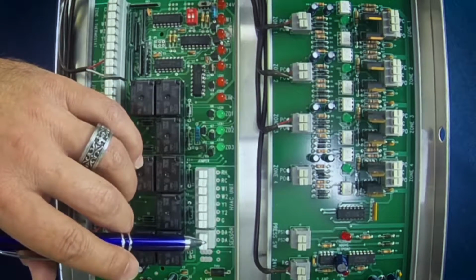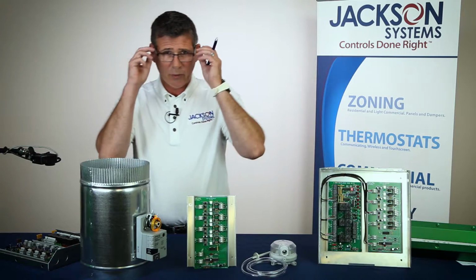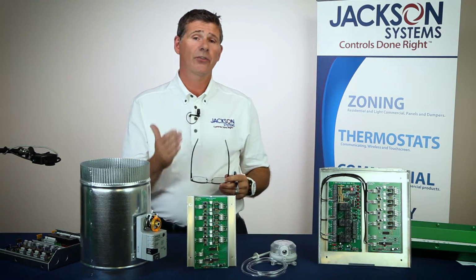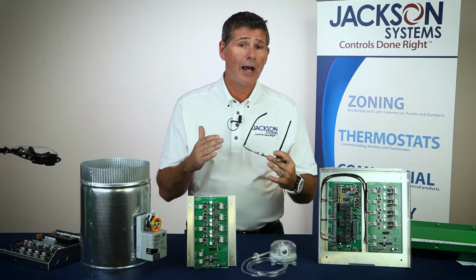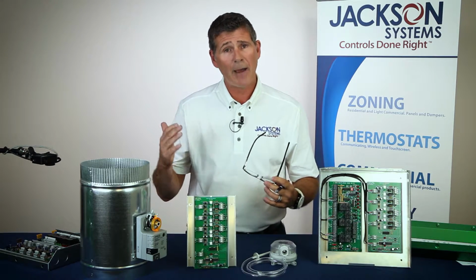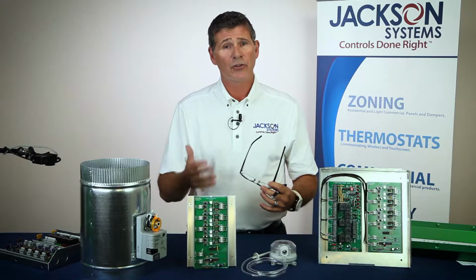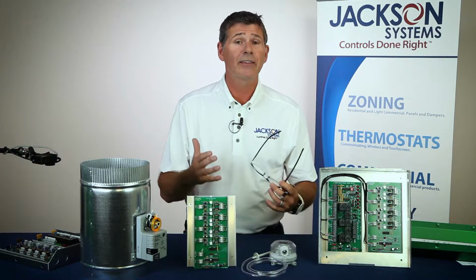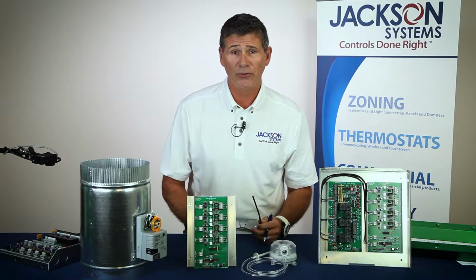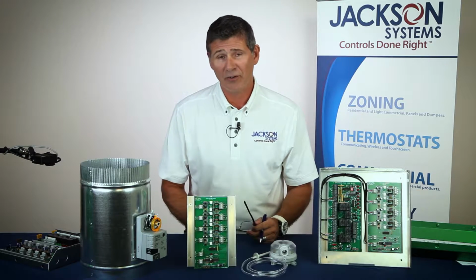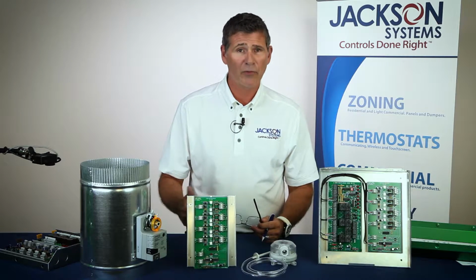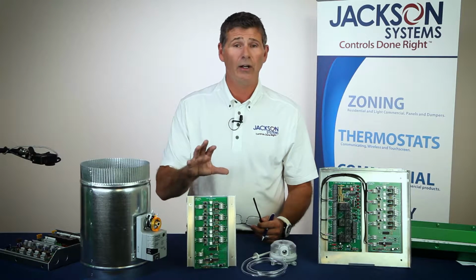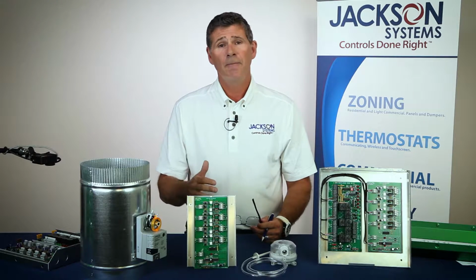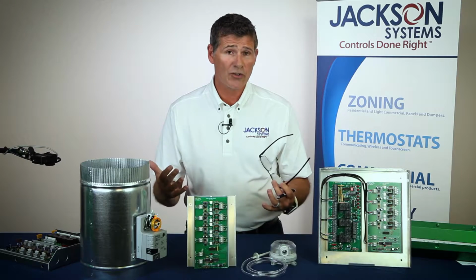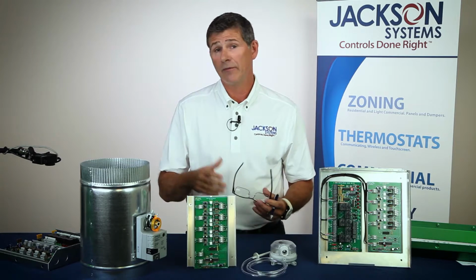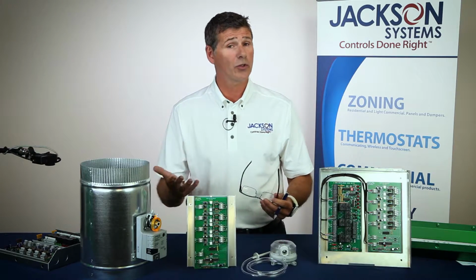Now I can tell you that with the discharge air sensor, you're absolutely going to want to wire in a discharge air sensor. Now even though we're not using a bypass system, so we're not bypassing air back through the system, you're still going to want to have a discharge air sensor in the event that the homeowner decides that for the next 6 months or so, or even longer, they don't want to change their air filter. So if you've got a clogged up air filter, you're also still running the risk of coil freeze up. So, and of course that's one of the largest concerns when you are bypassing air, when you have a bypass system installed. You want to make sure that your coil doesn't freeze up.